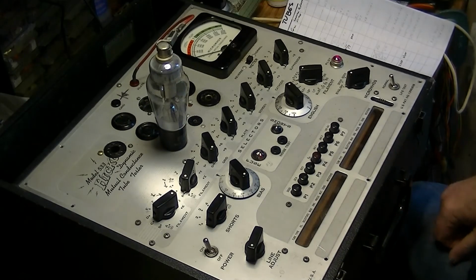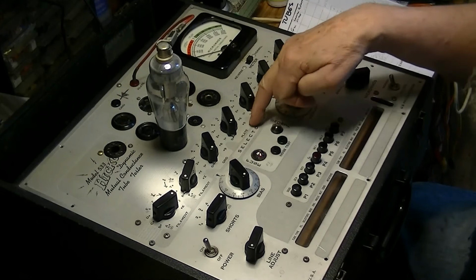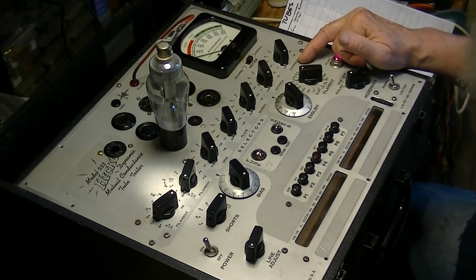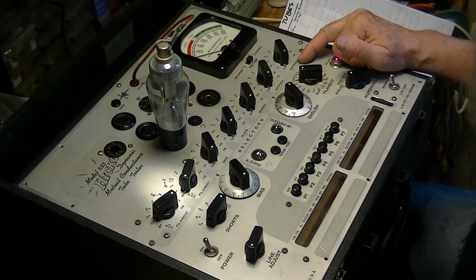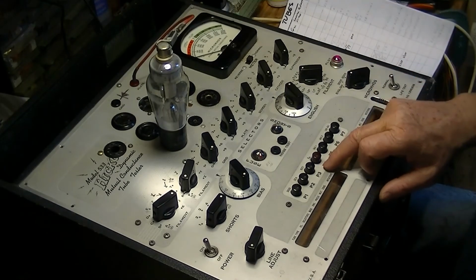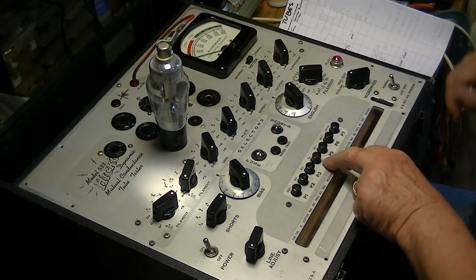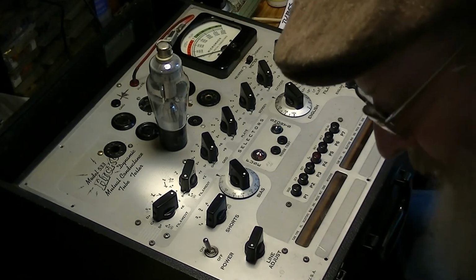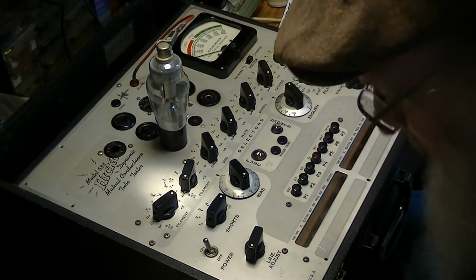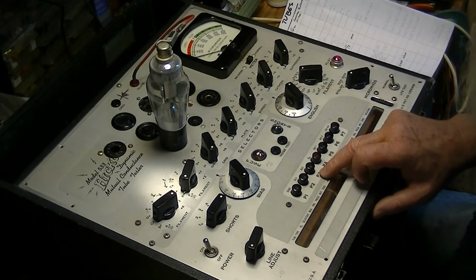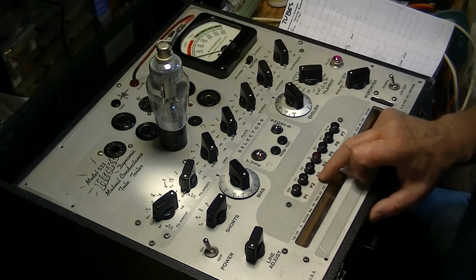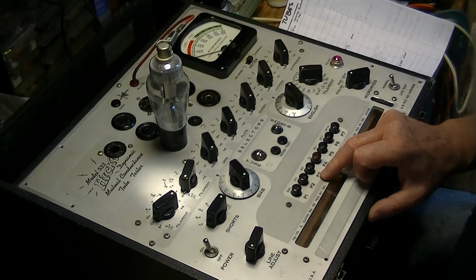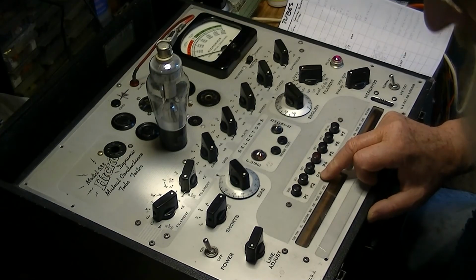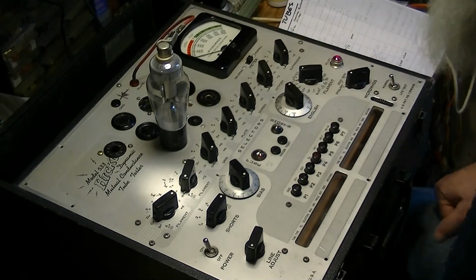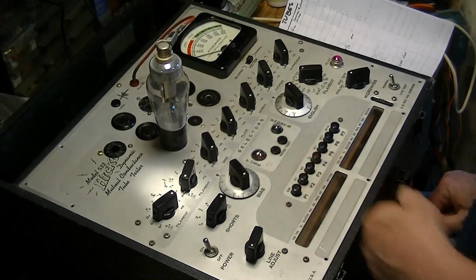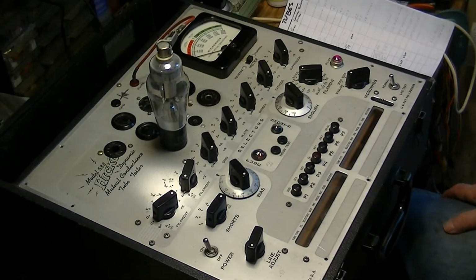So anyway, the testing drill for these, you notice that all these things are set to 0, and that's the way it's going to be for any rectifier. We're not going to use this P4, the transconductance test button. We're going to look in the chart, and the chart will tell us to use P3, which says rectifier. There's 2 or 3 different rectifier buttons here depending on which tube you're using, and this chart also reminds us to connect the cap, the plate cap. If you don't connect the plate cap, it isn't going to work.